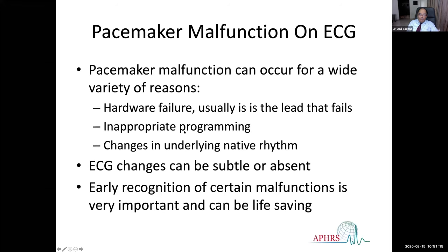Pacemaker malfunction can occur because of a variety of reasons. There could be hardware failure, and usually it is the lead that fails. Pacemakers usually don't have much problem; they're very robustly designed, but the lead is the weakest link.